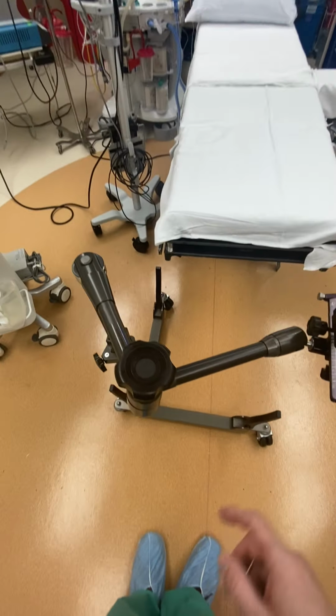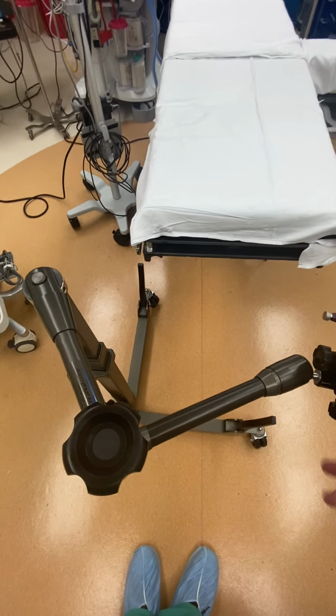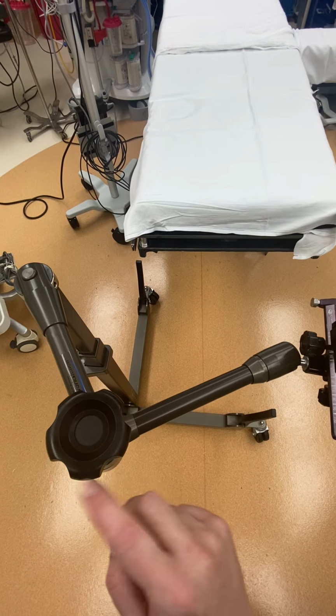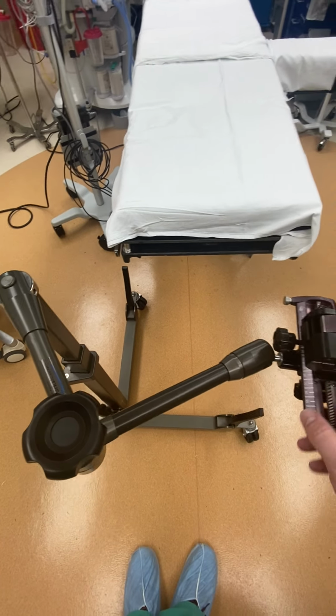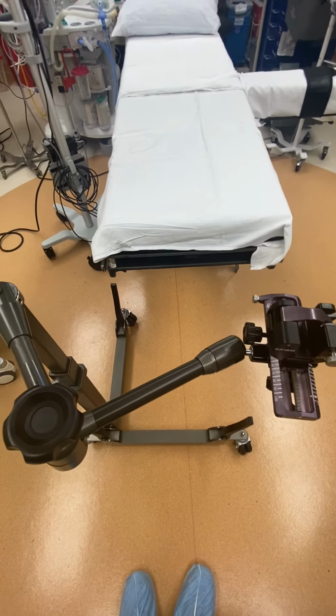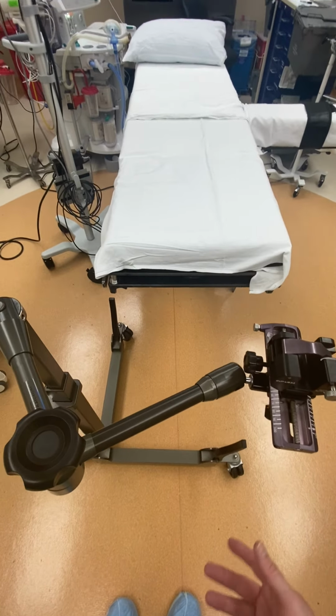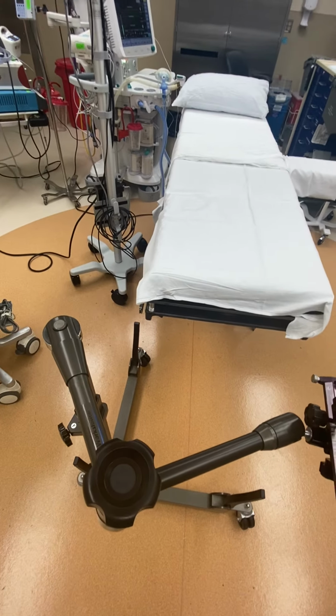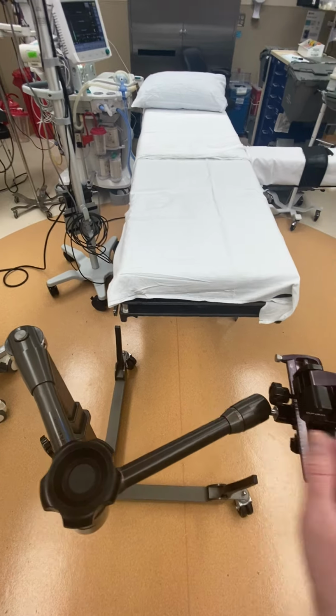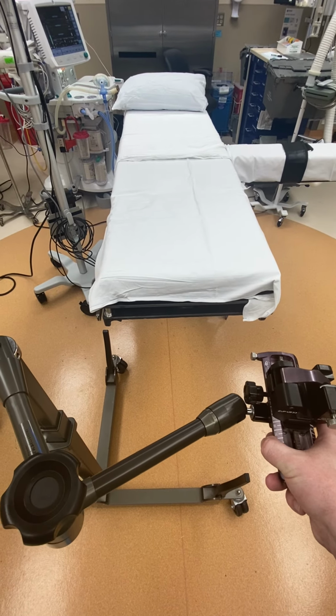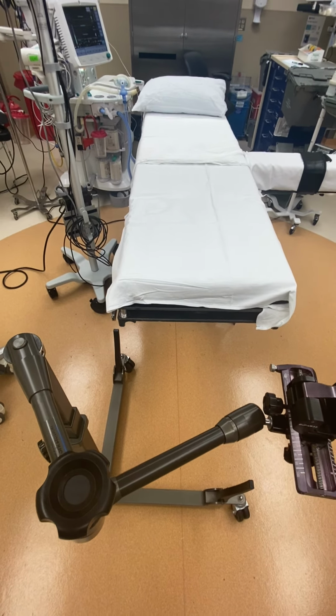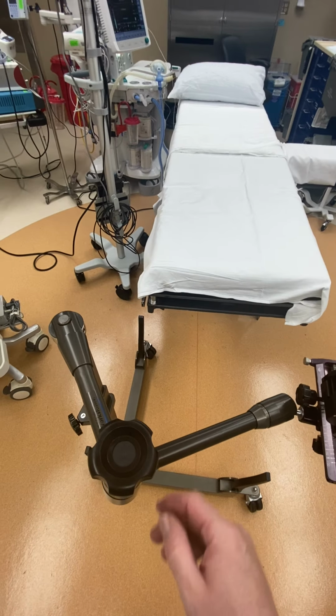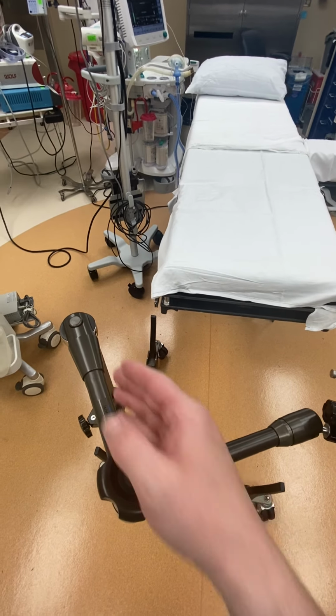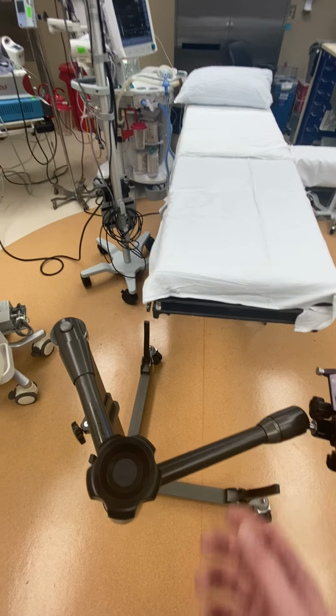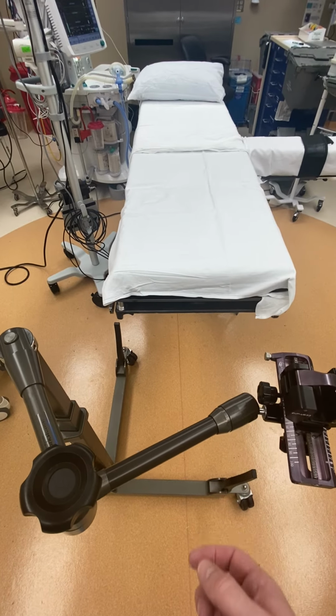You can see the arm is jointed, so you have to be careful when you loosen this bolt here. It'll make basically the arm and the cradle just drop, and you could risk damaging the probe. It could hit the floor, etc. So make sure that whenever you loosen this, you're holding the cradle so it doesn't drop. And sometimes you have to remind the urologist to do that. You want to make sure the arm is bending backwards, because that gives you a little more range of motion to go in and out.